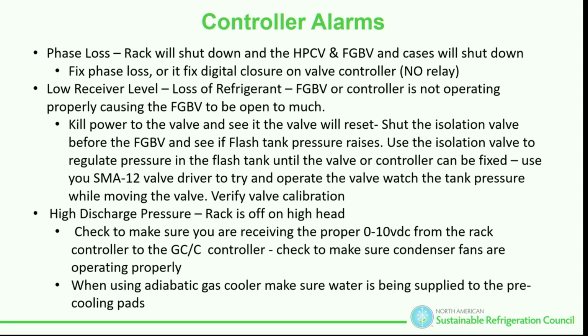It could be my high pressure control valve is too far closed. Check and make sure you're reading the 0 to 10 volt signal. That is a linear signal. It is not parabolic. It is a straight 0 to 10. If I'm reading 5 volts DC, how far open is my high pressure control valve? 50%. If you guys missed that, I would recommend an algebra class. 5 volts is 50% open.